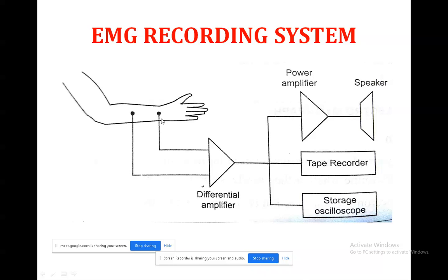So this is the EMG recording system. Here you place two electrodes, one acting as the active electrode and another as a reference electrode, which will be given to the differential amplifier. The biosignal collected from the skin surface or muscle is converted into electrical energy by the electrode in the transducer, and then given to the differential amplifier, which has a preamplifier and a difference amplifier.